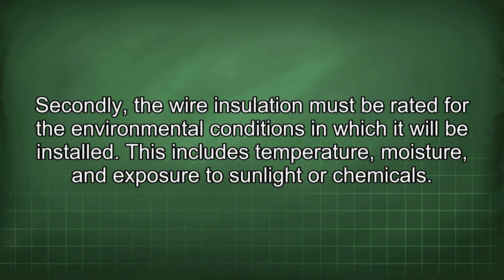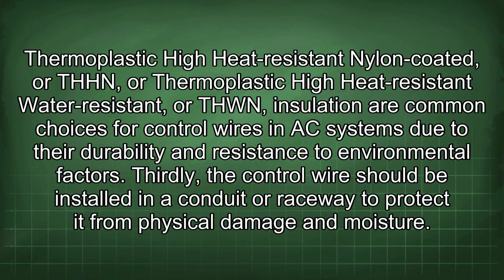Secondly, the wire insulation must be rated for the environmental conditions in which it will be installed. This includes temperature, moisture, and exposure to sunlight or chemicals. Thermoplastic high heat resistant nylon coated, or THHN, or thermoplastic high heat resistant water resistant, or THWN, insulation are common choices for control wires in AC systems due to their durability and resistance to environmental factors.